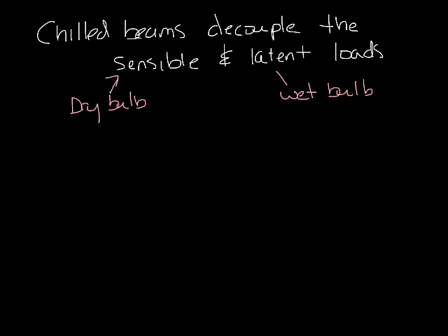Chilled beams decouple the sensible and latent loads in a space. You've probably found a dozen good explanations for sensible and latent load online. The engineering toolbox defines it as the sensible cooling load refers to the dry bulb temperature of the building, and the latent cooling load refers to the wet bulb temperature of the building. Think of sensible load referring to the temperature on a thermometer, and latent load referring to the humidity.